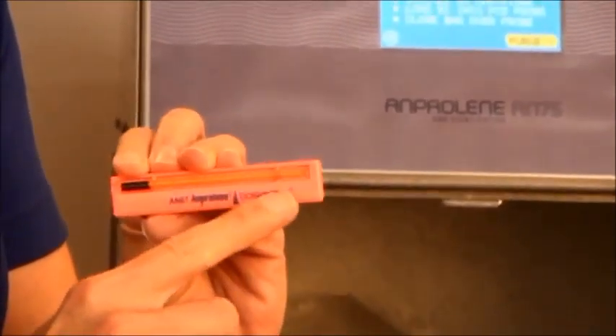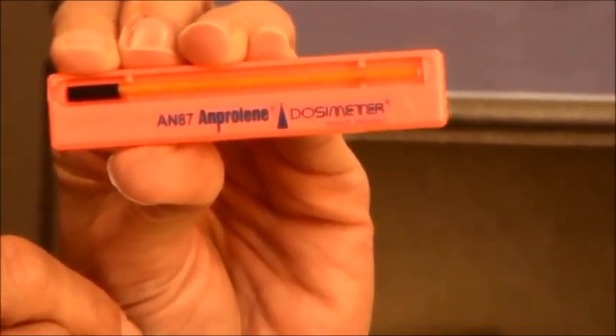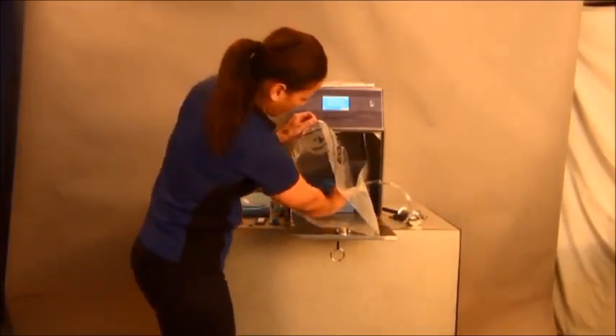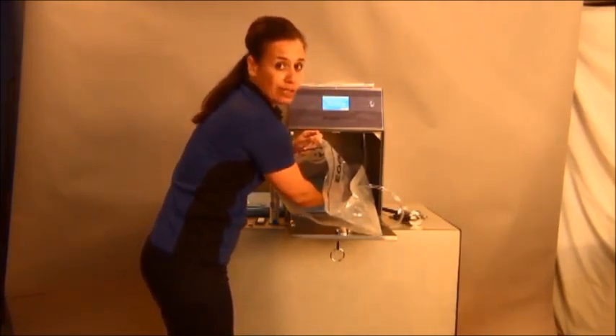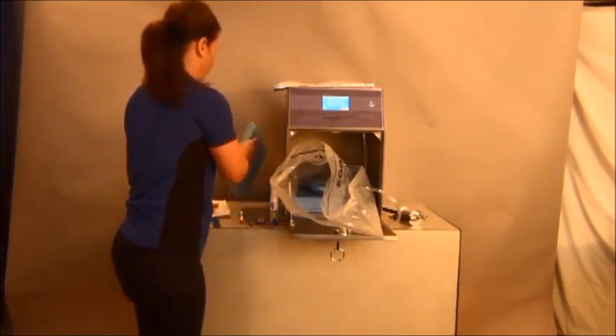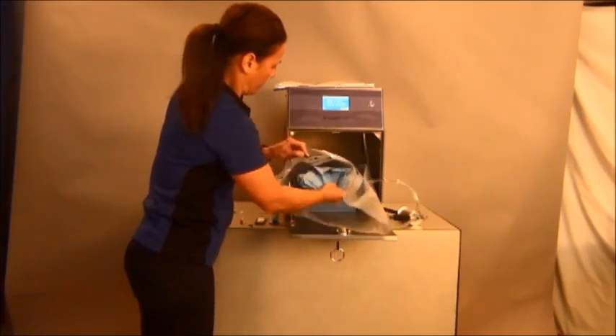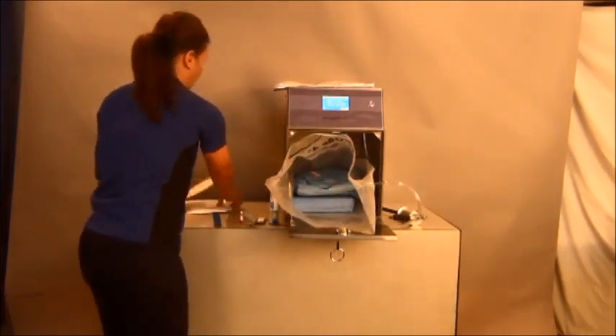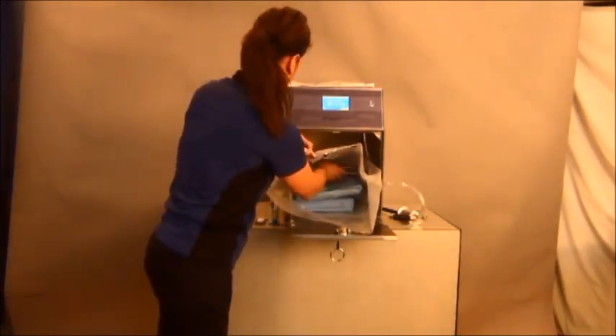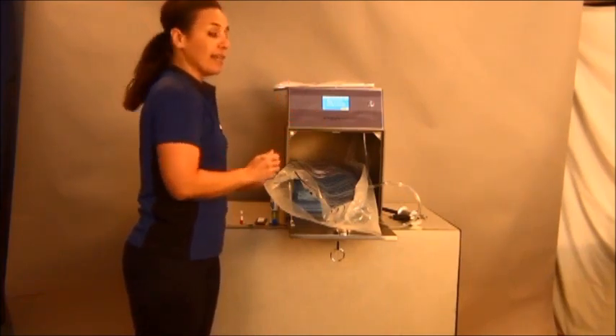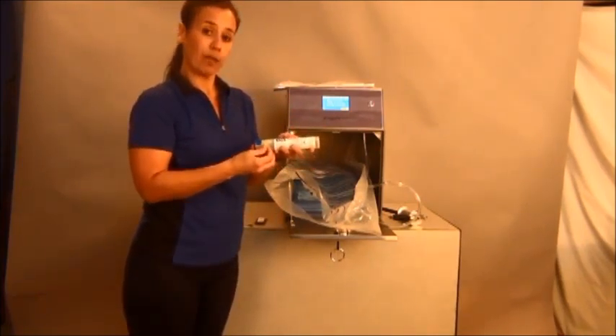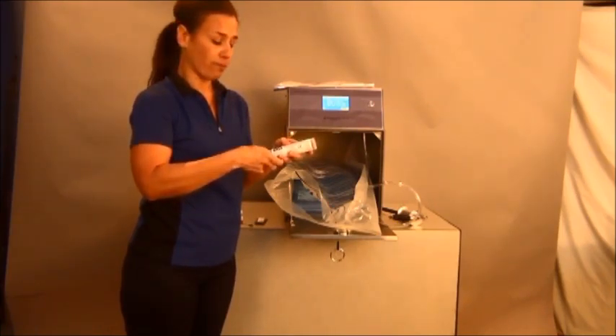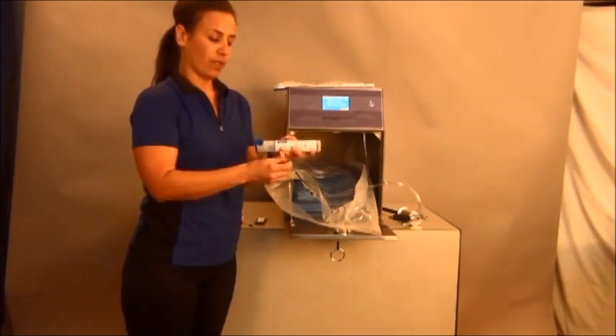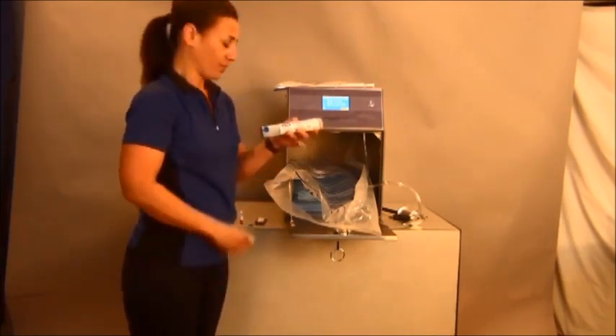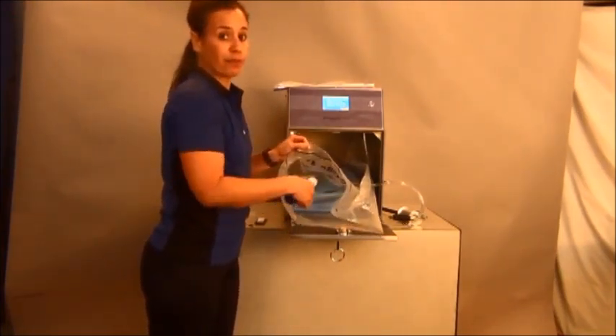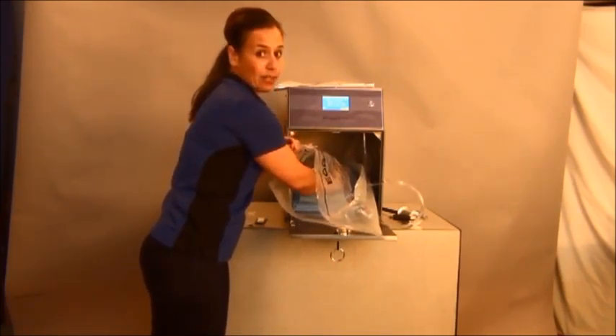As you can see, the capillary that runs across the middle is a gold color. So I'm putting it in between my items where I think it's going to be the most difficult place for gas to reach. The next step indicated is to add your ethylene oxide cartridge. Again, by removing the green tape that holds the trigger guard down, you want to remove the trigger guard. Place this on top of your items in a place where you can easily access the blue trigger.